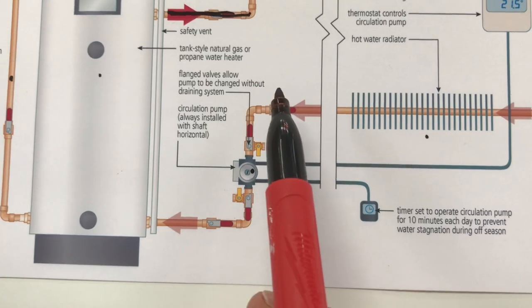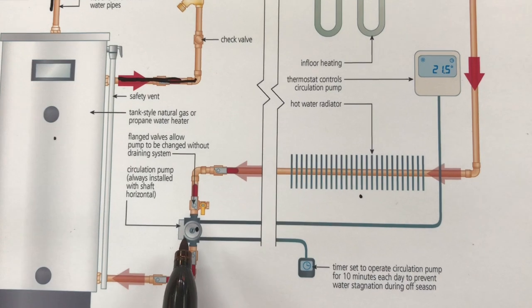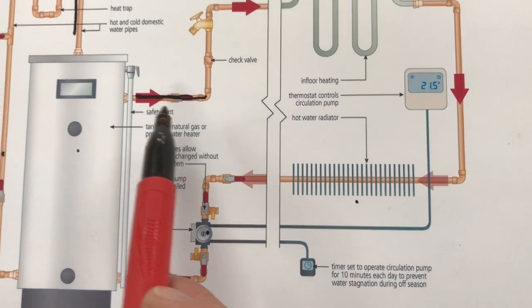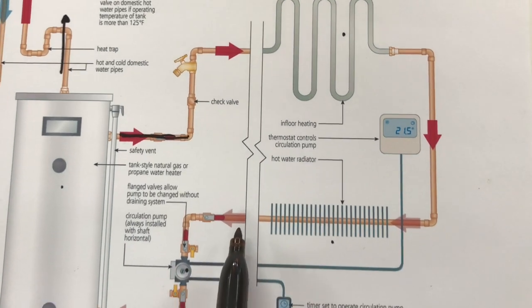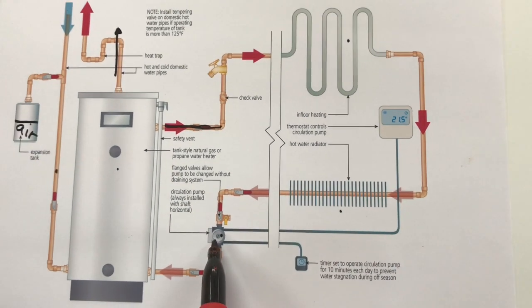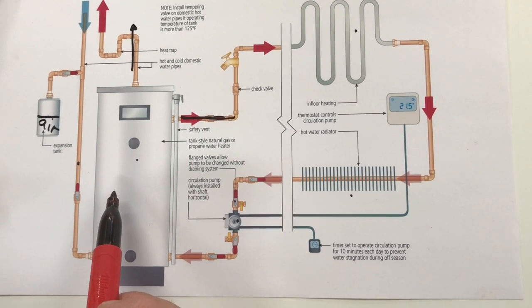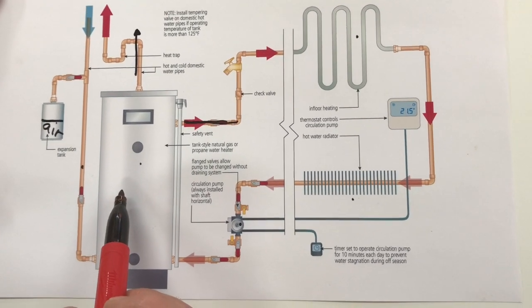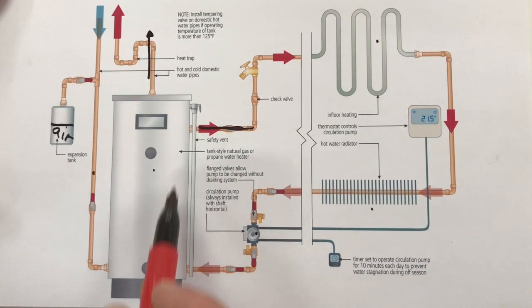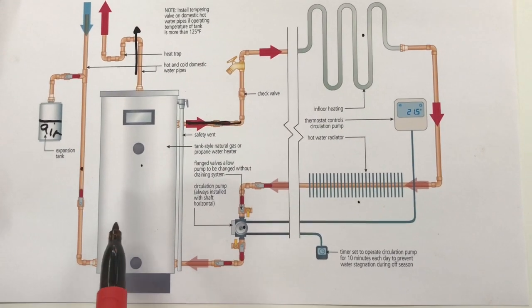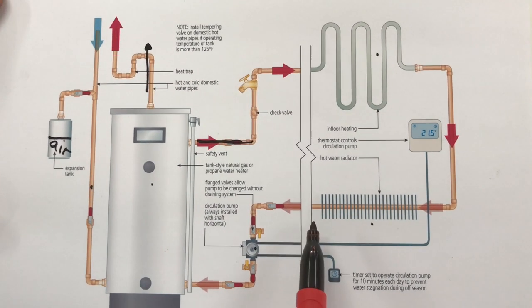So the thermostat calls for heat, turns on the circulator pump, circulates hot water through the system until the room is warm and then the thermostat shuts off the pump. Cooler water is returning to the tank and the tank has its own aquastat inside so it will fire up and keep the water in this tank hot as needed in a kind of separate loop.